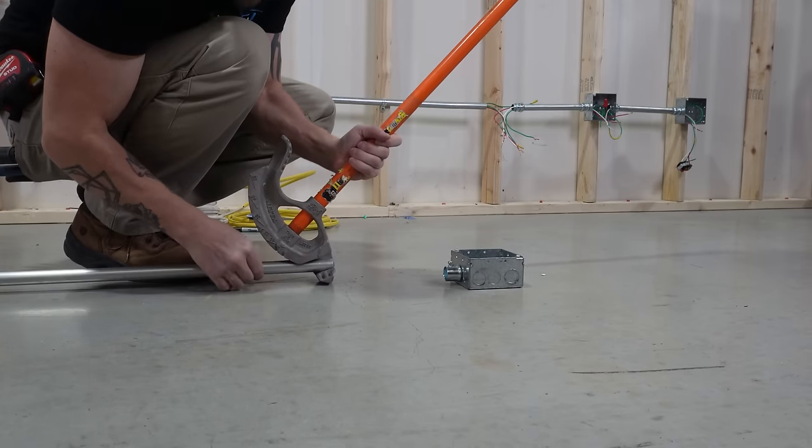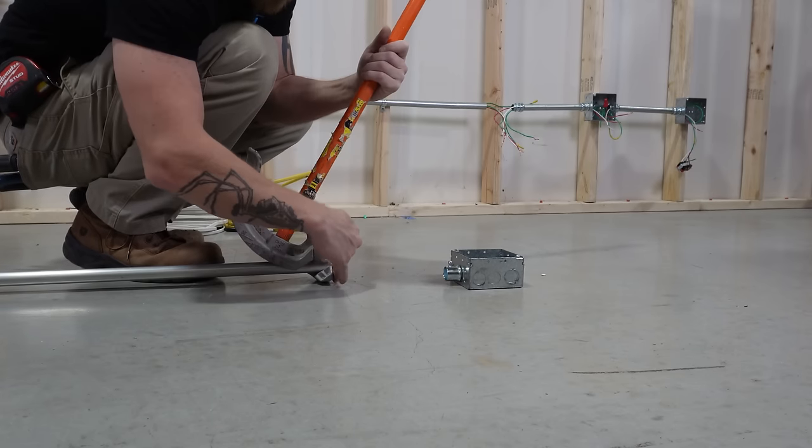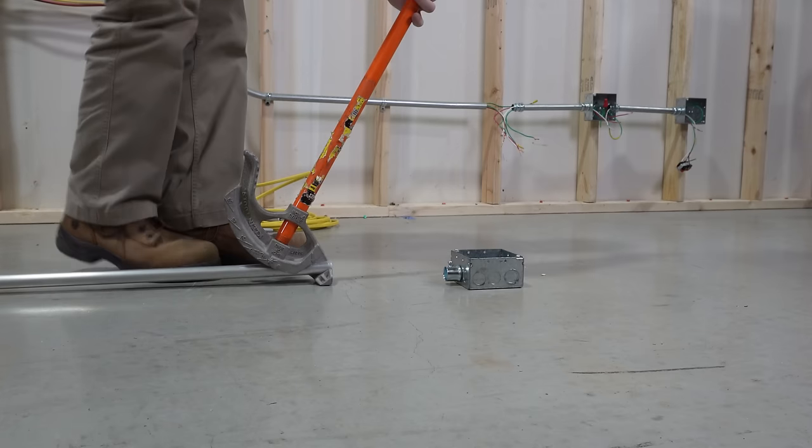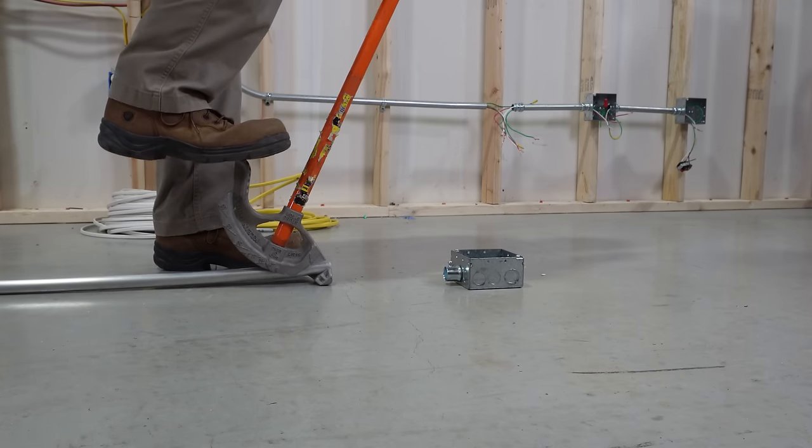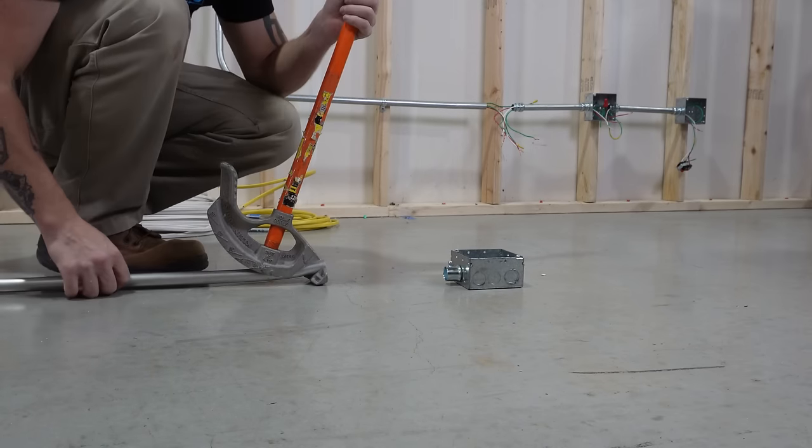I don't line my mark up. I don't mark it up like that. I leave this flush with the end of the bender. I don't draw any lines or anything. So all I'm going to do is a little bit of a kick. Look how incredibly little that was. You could barely see any movement on that.